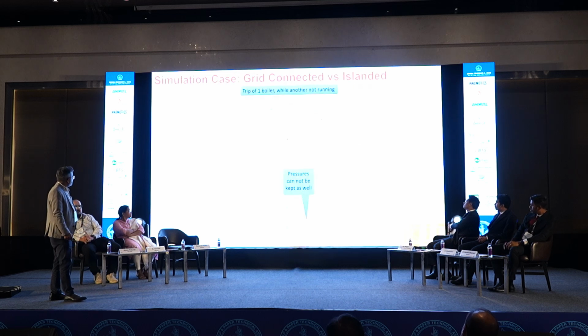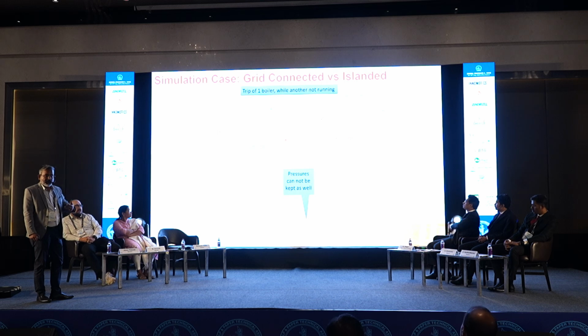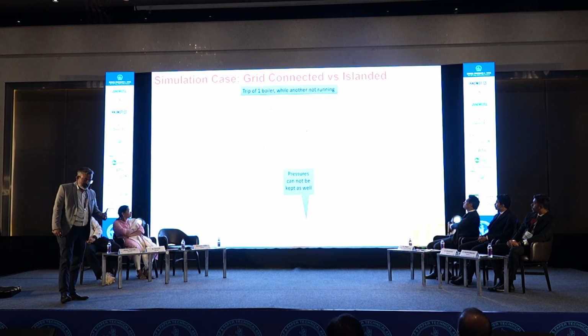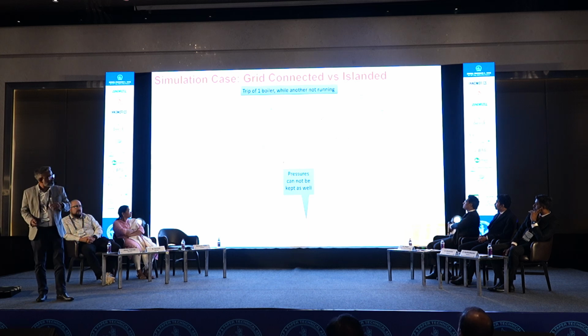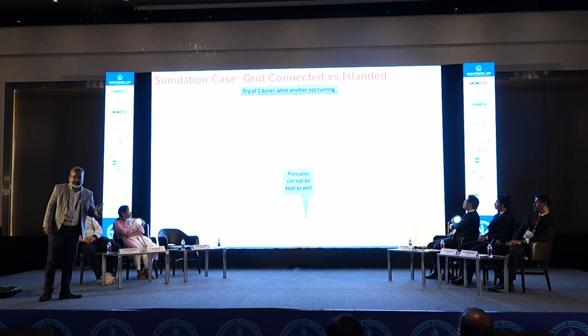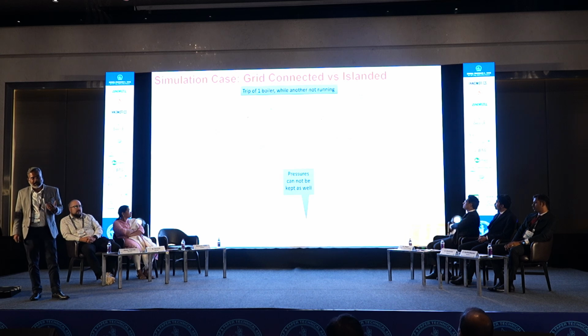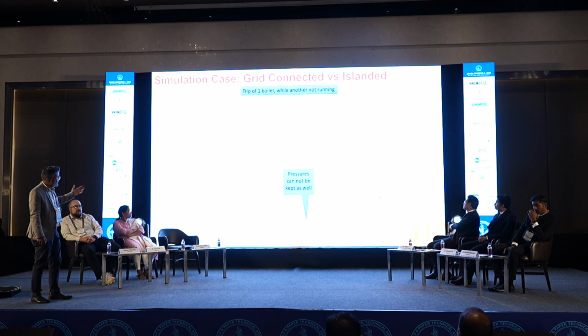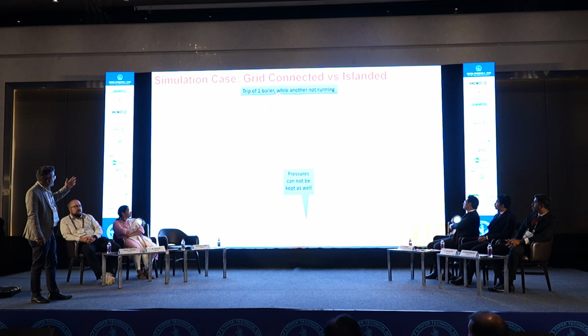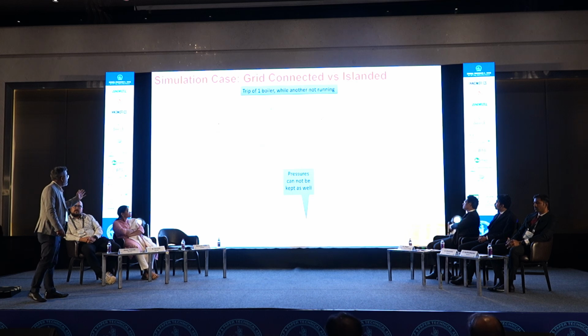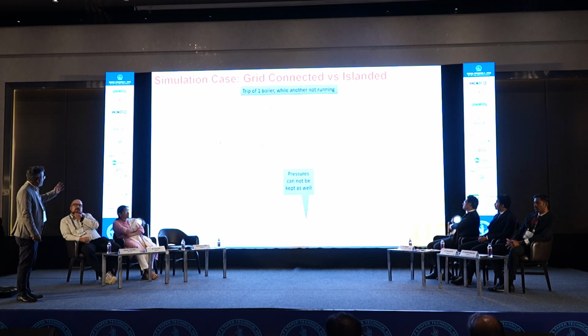And let's see a case. Then we run simulation cases, before we do this sensitivity study, to identify all the operating ranges of the plant. Then we study the anticipated scenarios that could come up in the plant. So for this particular case, we have seen the trip of one boiler while another was under maintenance, in both the cases, when the plant is grid connected as well as islanded. So on the left hand side are the grid connected graphs, and on the right hand side is the islanded.